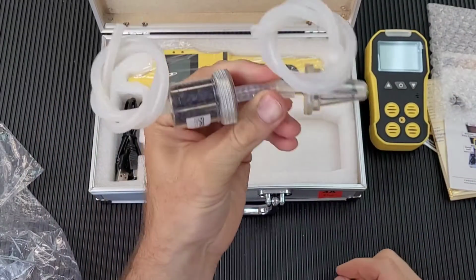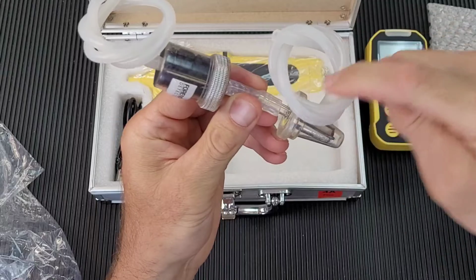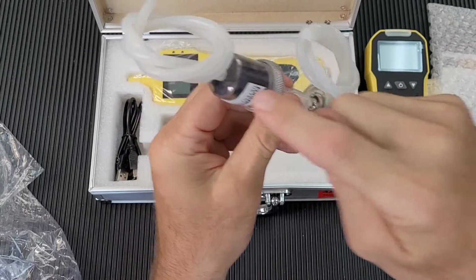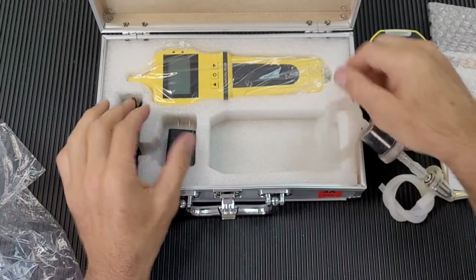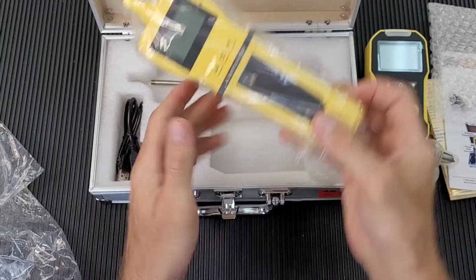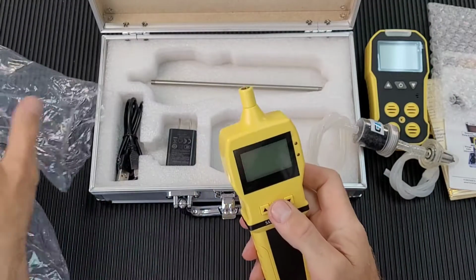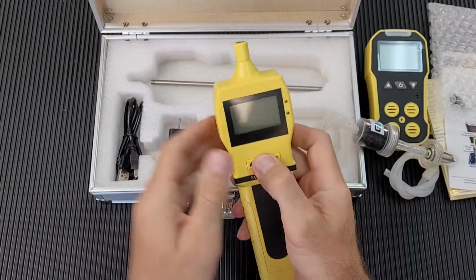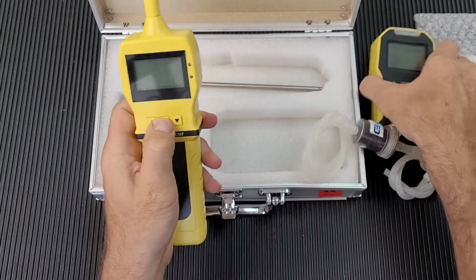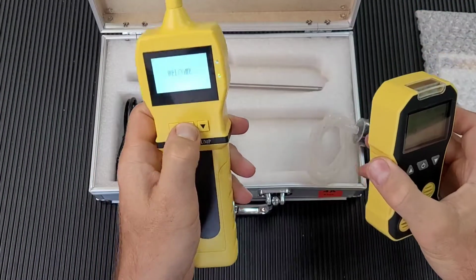What else are you going to get? You get your combustion kit, the line, water trap, and filter. We're going to put that all together, so you'll see how all this comes together, folks. And our pump, a handheld pump. So this is unlike the other units. This does not have a built-in pump, folks, so it's two separate units. We have the analyzer and we have the pump.